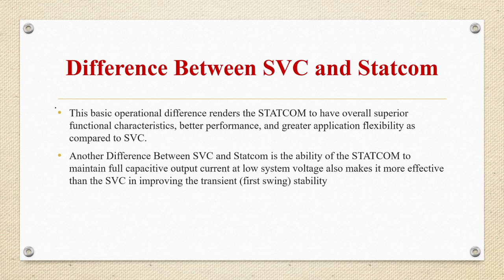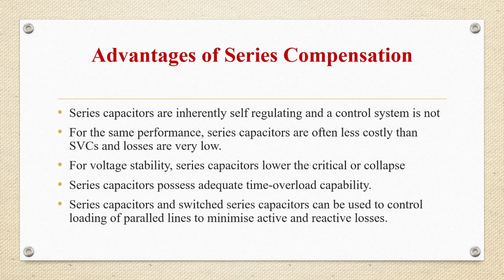Now let us see the advantages of series compensation. Series capacitors are self-regulating and a control system is not required. For the same performance, series capacitors are often less costly than SVC and losses are very low. For voltage stability, series capacitors lower the critical voltage for collapse, and they possess adequate short-time overload capability. Series capacitors and switched series capacitors can be used to control loading of parallel lines to minimize active and reactive losses. Now let us see the disadvantages of series compensation.